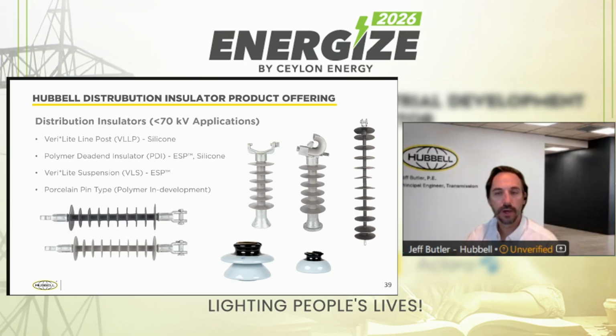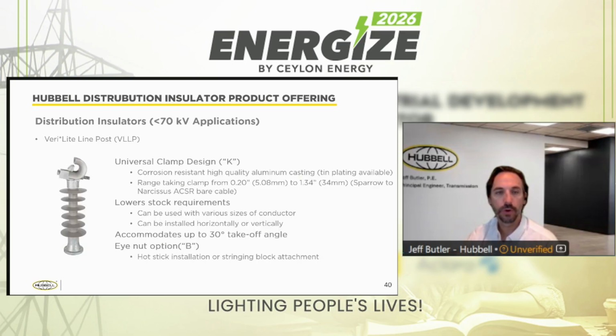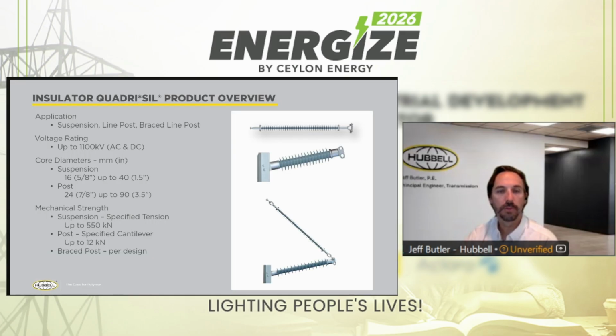Targeting just a little bit, one of our unique designs for the VLLP or Veri*Lite line post is a universal clamp. That's what's shown here in this image. This allows for the use of this product vertically or horizontally so that it will reduce your stock levels. You only need to keep one of these in stock because you can install it vertically or horizontally based on the desired application. When we're looking at transmission voltages, I went through a little bit of these sizes: suspension, line posts, and then a brace line post.